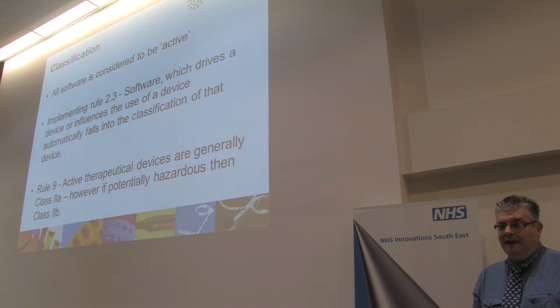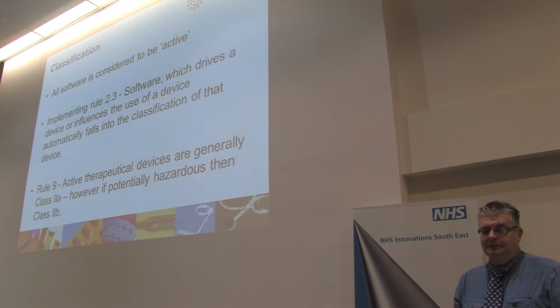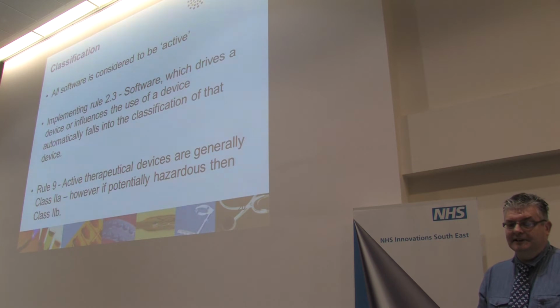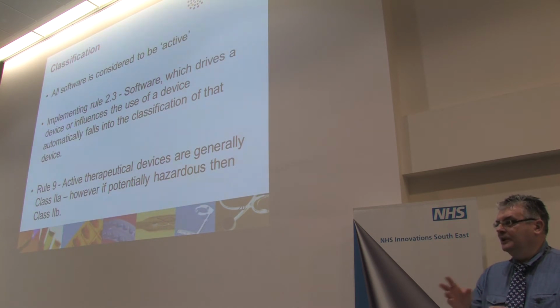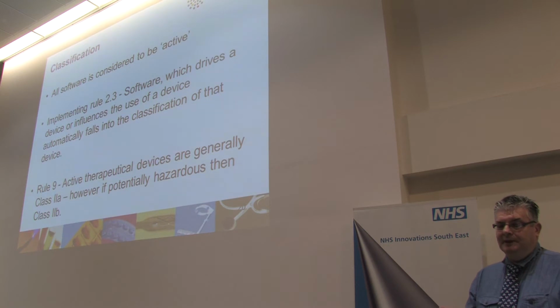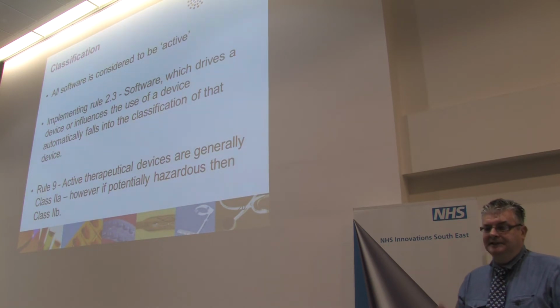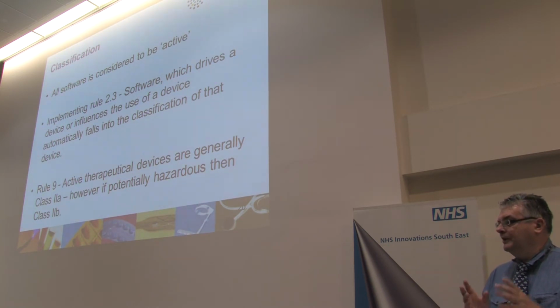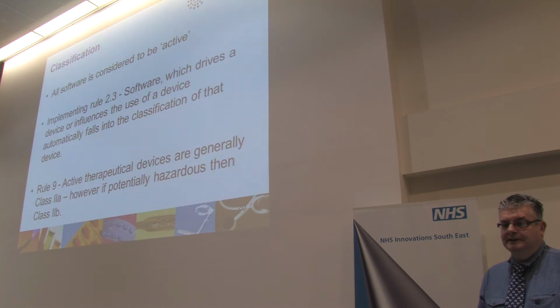Rule 9: an active therapeutic device is generally Class 2A, however if potentially hazardous then Class 2B. Most of the apps aren't therapeutic devices in their own right, that's where you're actually putting energy into the patient, but they could drive some of these devices. So if apps drive any active therapeutic devices, they will also fall into 2A or 2B, and this is where it becomes complicated because you have to have a notified body. It's a medium risk product, so a notified body would be needed to look at the quality system.